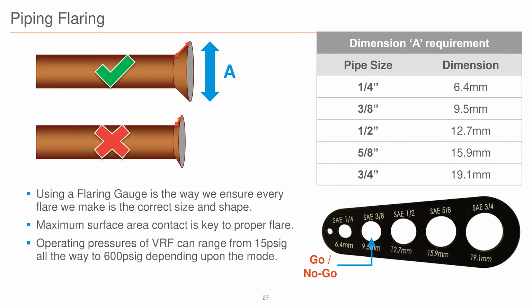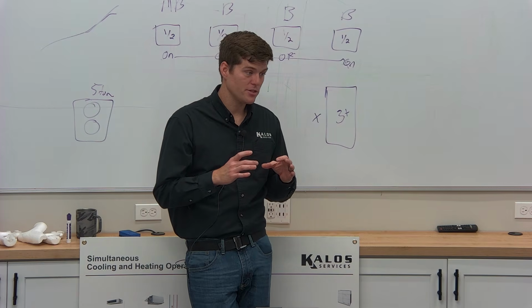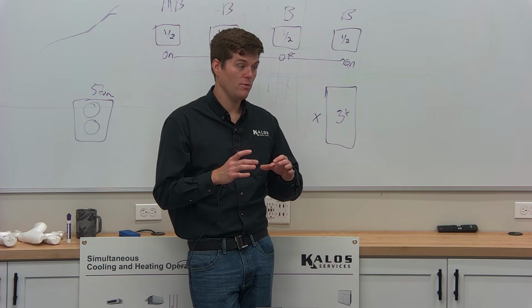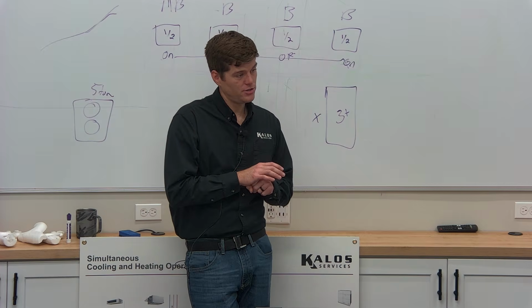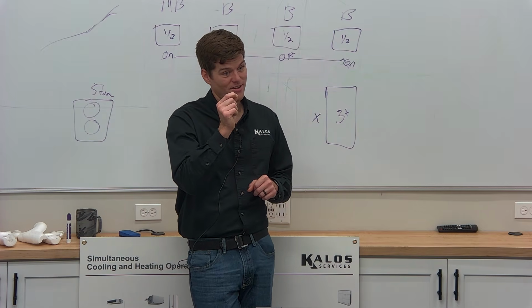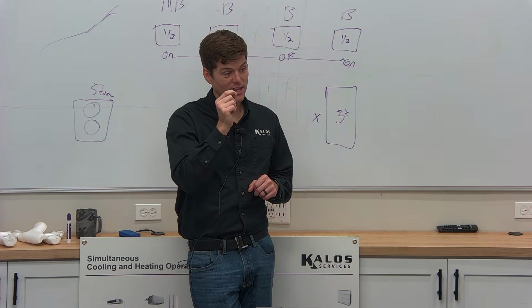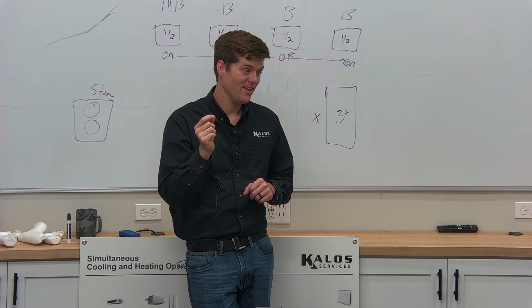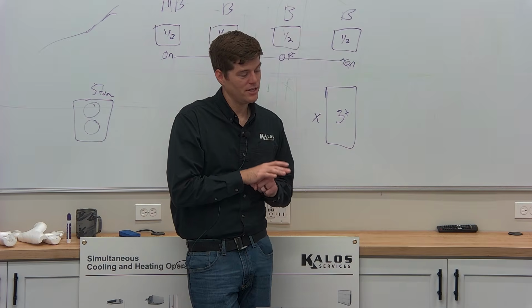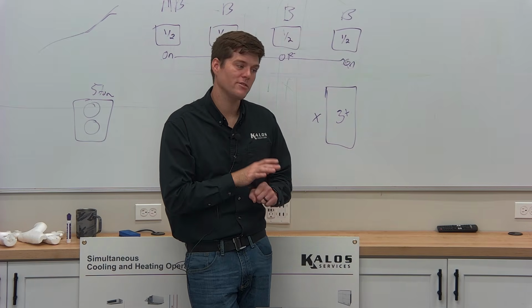That gauge, is that measuring the pipe size or the actual flare size? So it says that if you have a 1/2-inch pipe, when I flare that 1/2-inch pipe, it should fit into the 1/2-inch gauge at the end. So it's after you make the flare. It should fit in, but not pass through. Okay. When we have the flaring class, I'm going to show you. I bought a bunch of gauges for everybody. I bought a bunch of flaring tools for everybody. We're going to go through it. It's called a no-go gauge. There's actually a hair of bevel inside. When you see it, you're going to be like, there's no way. If it fits in the gauge and doesn't pass through, it's the perfect size. If it passes through, it's too small. If it doesn't fit in the gauge, it's too big.